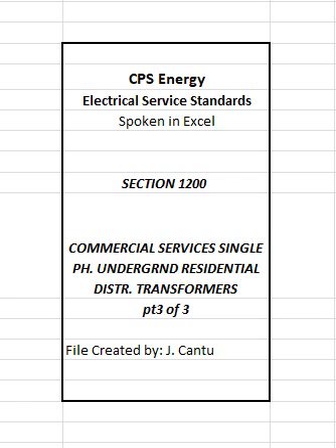The maximum number and size of service entrance conductors that may be connected to a CPS Energy secondary enclosure are limited to 3 to 350 kcmil conductors per phase. Where customer elects to install conductors in excess of 3 to 350 kcmil per phase, the primary will be required to extend onto the property and a new transformer must be installed. A tap box may be required if service entrance conductors are in excess of that allowed by Table 1201. 1205.5 Tap boxes.